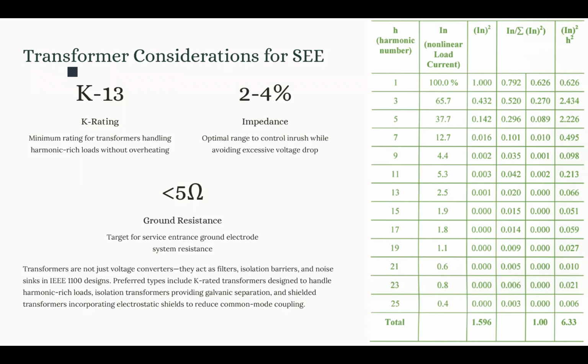Another aspect that we need to keep in mind when we choose the proper transformer is the ground resistance. The limit recommended by IEEE 1100 is less than 5 ohms for the service entrance ground electrode system. This 5 ohm is the target for the entrance ground. But IEEE 1100 emphasizes that we have to have less than 1 ohm for the signal reference. Make sure that you distinguish these two. The purpose of the less than 5 ohm is to make sure that we have a uniform ground reference for sensitive electronic devices, and it prevents the potential difference that could cause common mode noise.